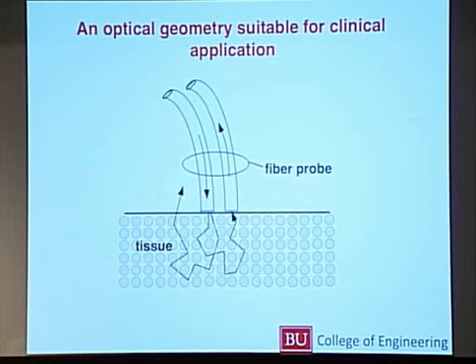But if it's a hollow organ like the colon, we can get there with a fiber optic probe, and we make the geometry such that these fibers are small and very close together. So the separation of these fibers is less than 3/10 of a millimeter, so 300 microns or less. So these source and detector are very close together. So most of the light that's collected by the collection fiber are photons that have scattered a small number of times, 2, 3, 4, or maybe only one time, whereas photons that scatter a larger number of times propagate a significant distance, typically are lost. They either come out somewhere else or get absorbed down below there. But if it happens to turn around 180 degrees within a small number of scattering events and gets collected, then we're actually becoming very sensitive to the details of the scattering mechanism.